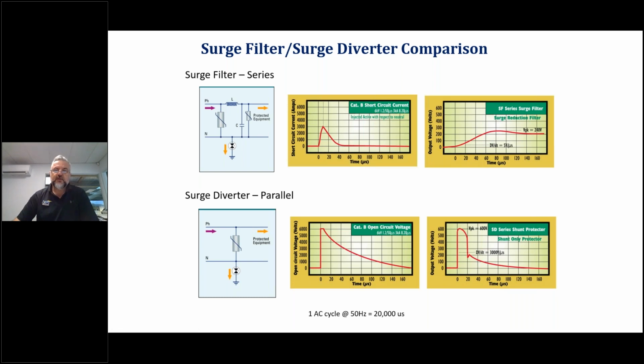So if you require superior surge protection, then you should look at a surge filter, which is particularly more cost effective on any currents up to 125 amps. Very comparable with the pricing of the surge diverter. But the main advantage of the surge filter is that it has LC circuitry, so it has a capacitor and inductor. It also has metal oxide varistors on the front and back end. The main advantage, as you can see here, is that the let-through voltage will be only about 230 volts when compared with the 600 volts with the surge diverter.